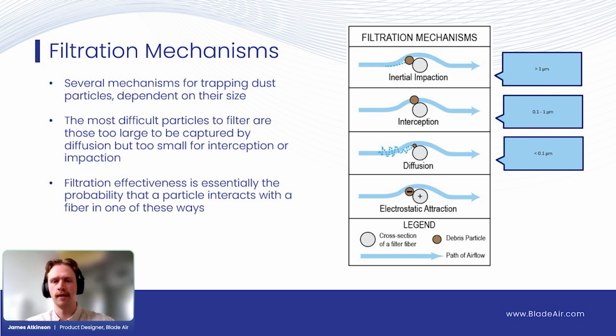The smallest one is diffusion, so that's less than 0.1 micron. And this is actually Brownian motion. If you ever looked at something under a microscope and you see everything jiggling around, that motion is actually caused by the dust particle interacting with air particles. The individual air molecules are hitting that dust particle and making it move because it's so small, it's able to be affected by just those tiny particles. So these tiny particles will exhibit a sort of random motion, and it's very likely that through their path through the media, one of those random motions will cause it to bump into a filter fiber and become caught.